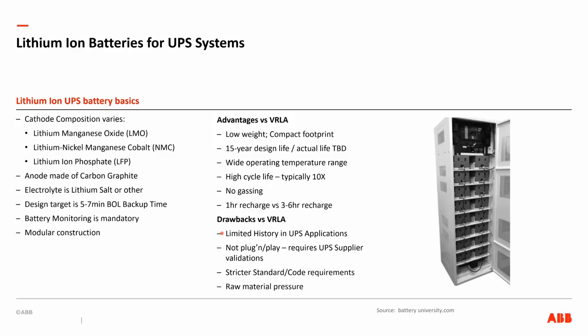A lithium ion battery solution is a solution. It's a battery in a cabinet with its monitoring. It's not like a lead acid battery off the shelf, where a 300 amp hour battery has the same physical dimensions and almost the same weight no matter what manufacturer, and is available off the shelf in a lot of different places. There's not the same flexibility. A lithium ion battery is bought or sold as a system. And I will get a little bit more into this, there are some stricter standards, especially in the last year, that put stricter requirements especially on lithium ion batteries.